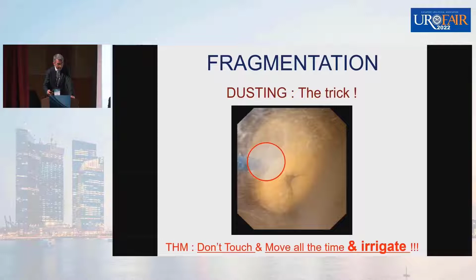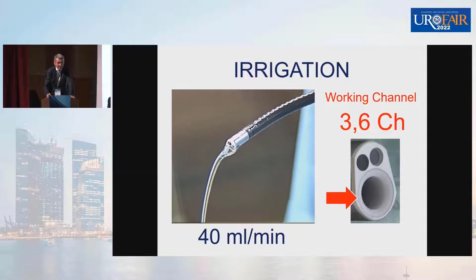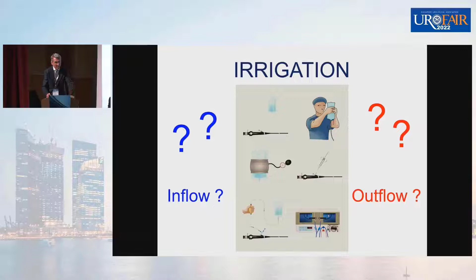Irrigation using a 3.6 Charrière working channel is more or less 40 milliliters per minute if the working channel is empty, and if you are using a pressure to irrigate of 40 centimeters of water, 40 milliliters per minute is enough. It's largely enough to work. The problem is that when you insert an instrument into the working channel, the flow goes down. So we need to increase irrigation to obtain a good flow.